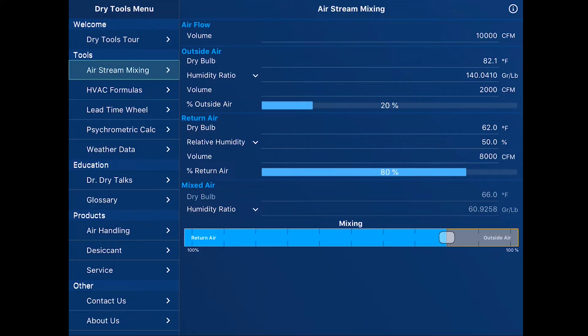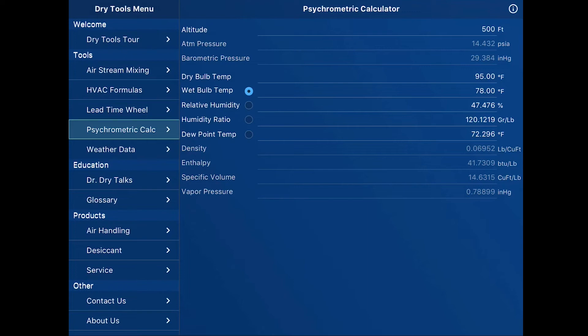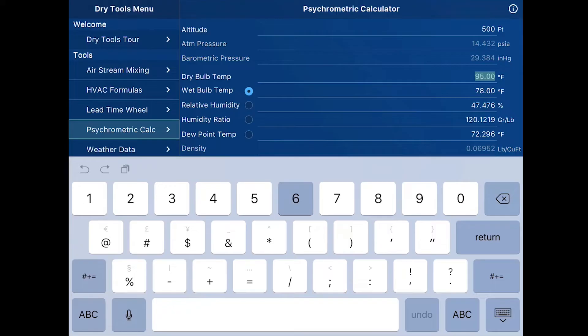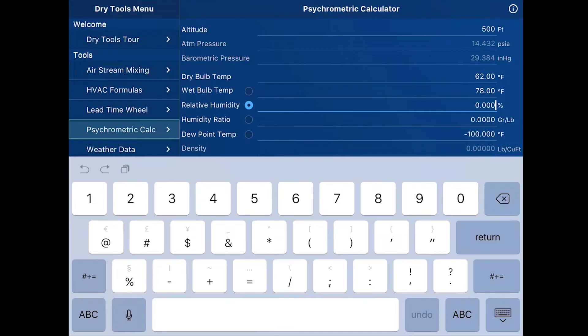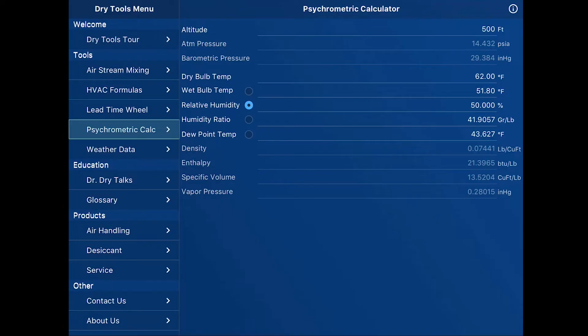The lower right hand corner now gives us our mixed air condition of 66 degrees dry bulb and approximately 61 grains. That's the mixed air coming in to the air handler or the desiccant machine. The next tool we'll look at is the psychrometric calculator. From our menu, I can push psychrometric calculator, and I can type in any two conditions. Let's go ahead and go back to that hospital surgical suite at 62 degrees and 50% relative humidity. Now we have all the other points on our psychrometric chart. Notice in the lower right hand corner, vapor pressure of 0.28 inches of mercury.